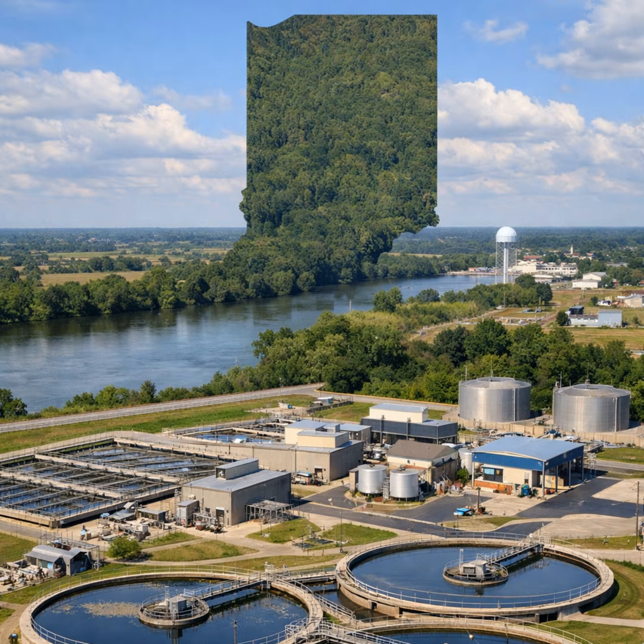Phosphorus stripping. What is phosphorus stripping? The effluent is run into a tank and dosed with a product known as a precipitant, such as alum or lime, which combines with phosphate in solution to create a solid, which then settles out and can be removed.